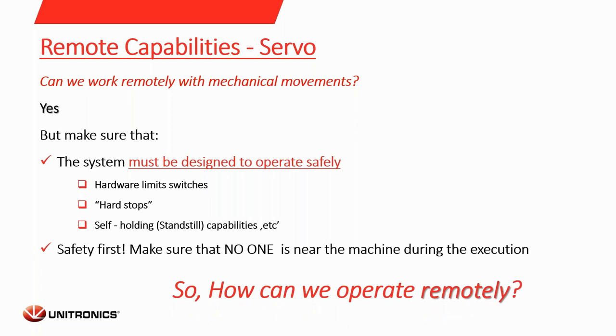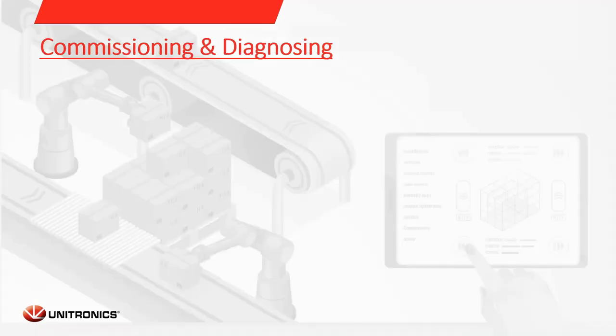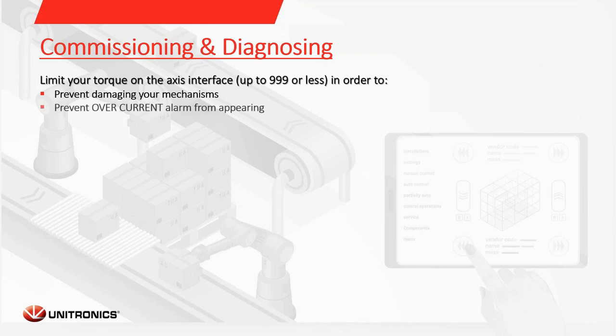So how can you work and operate the system remotely? The first phase would be commissioning. When we define the servo axis, I recommend you to limit the torque on the axis interface to a value less than 1000 — it can be even less. The first reason is to prevent damaging your mechanics, so on the first operation you should limit the torque so that if something goes wrong, no damage will occur.